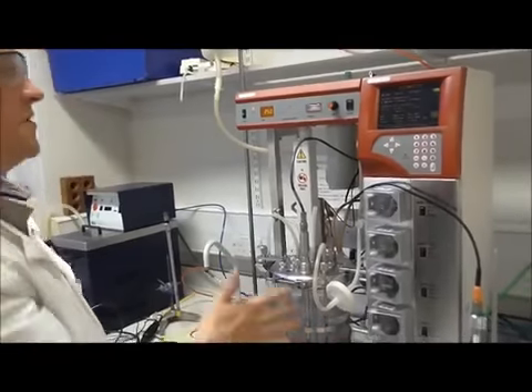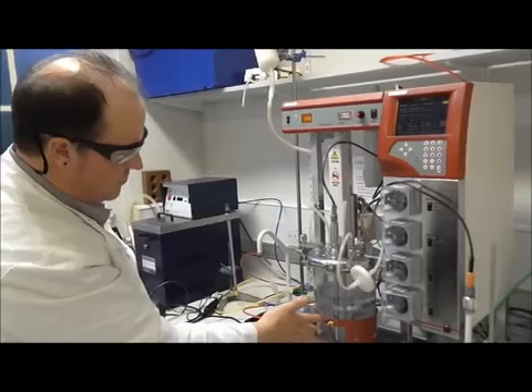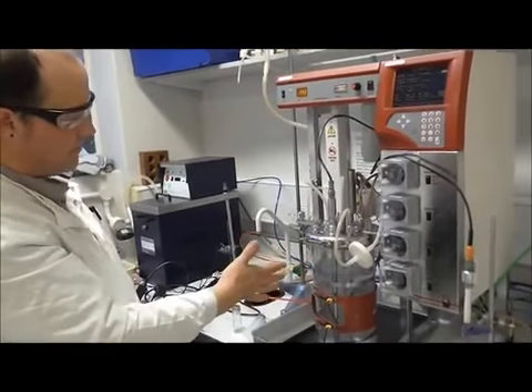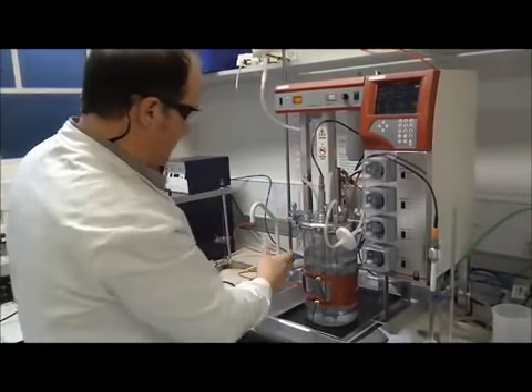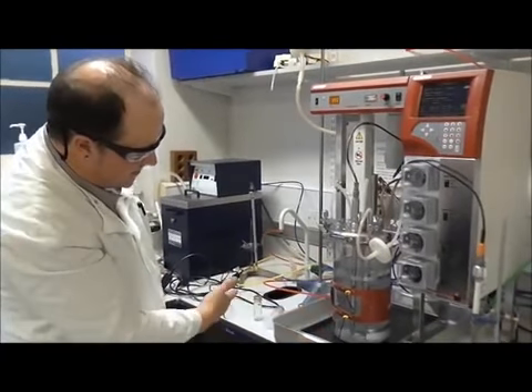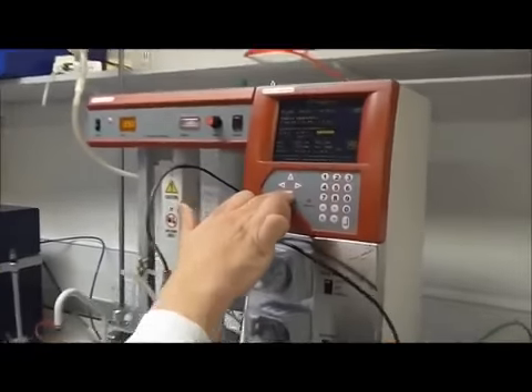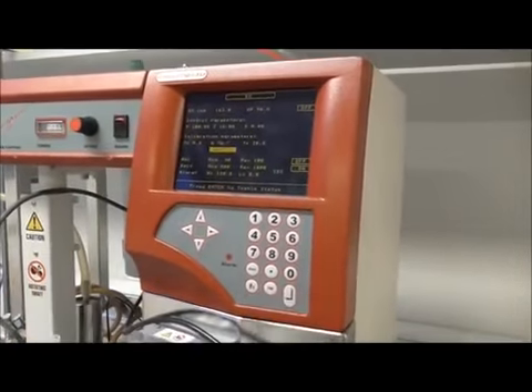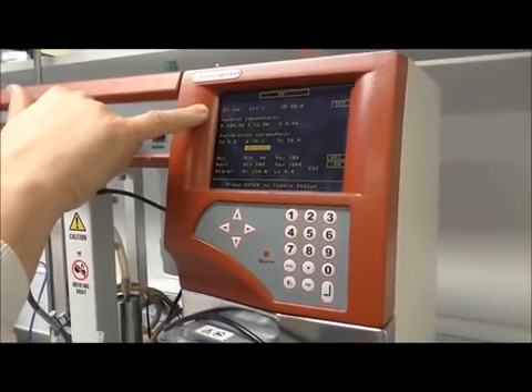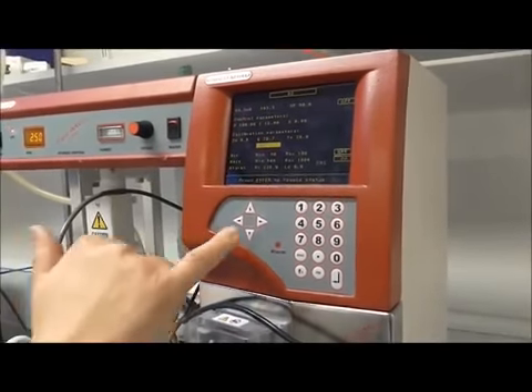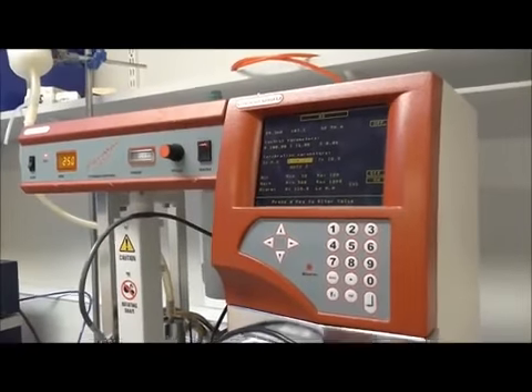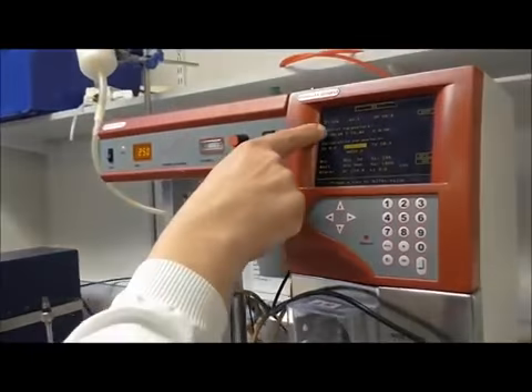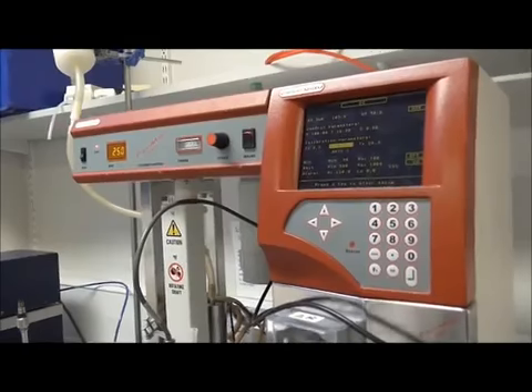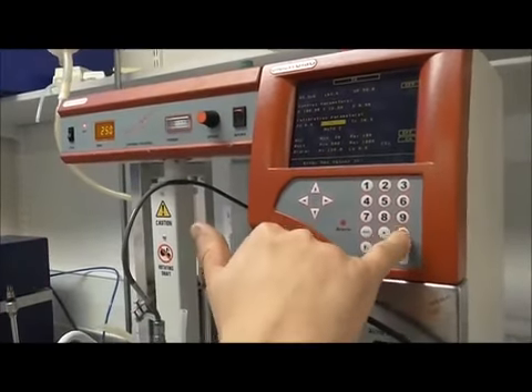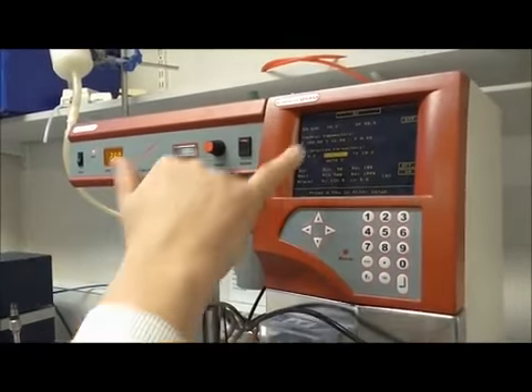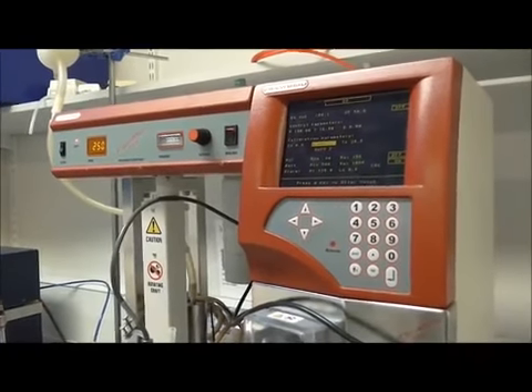Right, dissolved oxygen is pretty straightforward to calibrate. First of all, we need to allow this to run ideally for several hours to allow the probe to polarise and settle down. But once we're sure that the vessel is all nicely aerated, we scroll the cursor block down to auto 0. Now we press enter, and very briefly this will flash over to 0 and then back up again. To set 100%, we simply go up to G for gain, and we tell the controller the signal that this probe is picking up, and that 59.3 nanoamps is equivalent to 100% dissolved oxygen. So we're on G for gain, we go 100.0, oops, enter, and then that is set in. So very simple, very straightforward to calibrate.